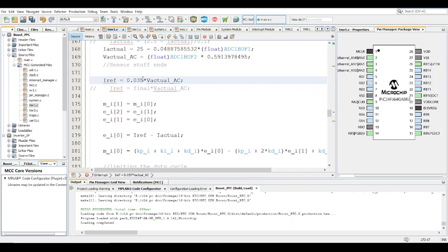I recommend you use a calculator, but I don't have one here. So you just basically choose a value here such that the Iref, the maximum Iref you'd get, if this was 325.269, the maximum value you get here would actually be 10. So it'll be 10 divided by 325.269, which gives you a value here. Or you could take this down more if you wanted that max value to be 5 amps. That's the first thing to do, right? Remember, you're just trying to see if you can make the current look sort of sinusoidal.